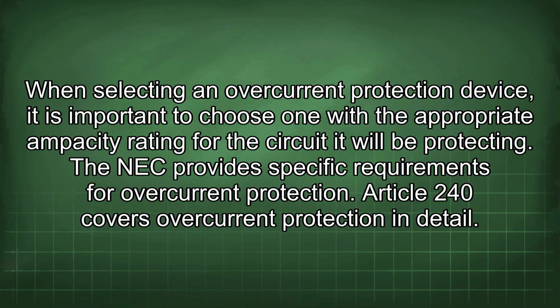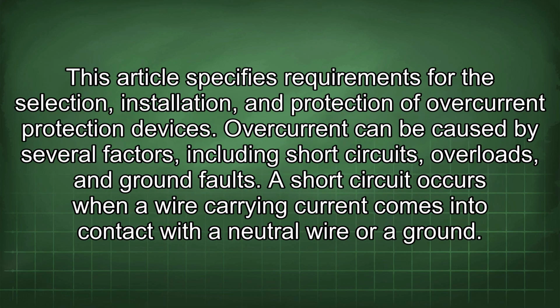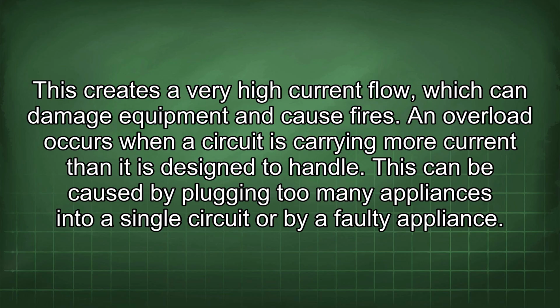When selecting an overcurrent protection device, it is important to choose one with the appropriate ampacity rating for the circuit it will be protecting. The NEC provides specific requirements for overcurrent protection. Article 240 covers overcurrent protection in detail. This article specifies requirements for the selection, installation, and protection of overcurrent protection devices. Overcurrent can be caused by several factors, including short circuits, overloads, and ground faults. A short circuit occurs when a wire carrying current comes into contact with a neutral wire or a ground. This creates a very high current flow, which can damage equipment and cause fires.